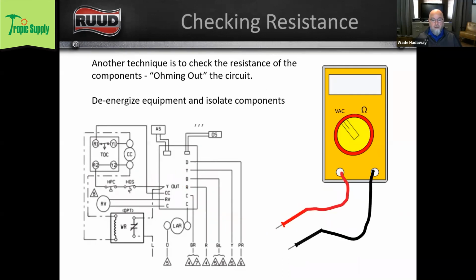Looks like I've got a duplicate slide in there. So there's another way that we could check this circuit to see which switch is open or what's causing us to have a problem there. We can check resistance on all these components, which is pretty commonly referred to as ohming out the circuit or ohming out the switches, right? So I would say I'm going to ohm out my hot gas sensor. I'm going to ohm out my high pressure control. And then if I don't find anything weird, I'm going to ohm out my contactor coil.